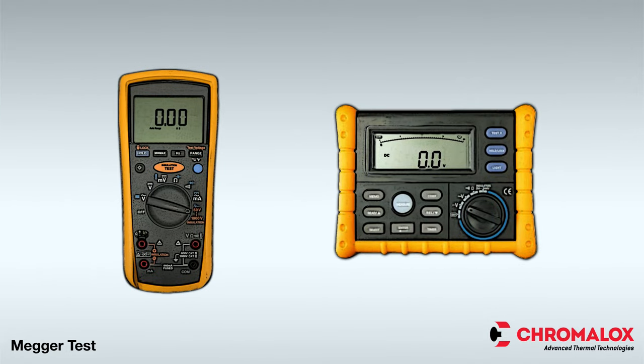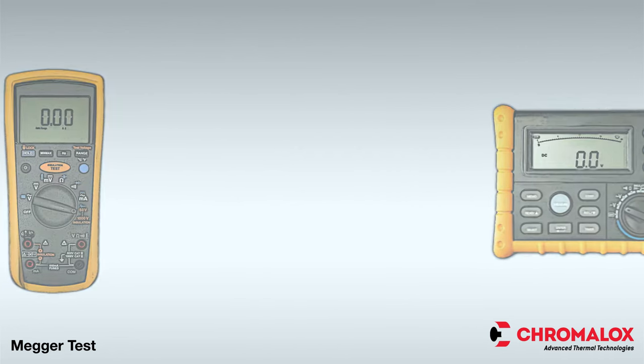In order to perform a Megger test, you will need an insulation resistance tester, also known as a Megger. The Megger should be a minimum of 1000 volts DC, but using a 2500 volts DC Megger is best. If possible, use a battery operated Megger; however, a digital or analog Megger will work as well.